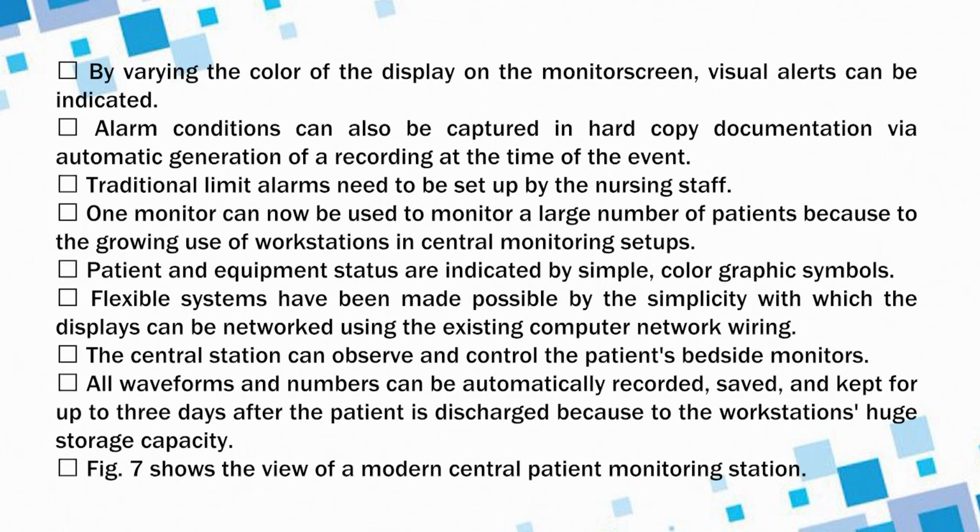The central station can observe and control the patient's bedside monitors. All waveforms and numbers can be automatically recorded, saved and kept for up to 3 days after the patient is discharged because of the workstation's huge storage capacity.